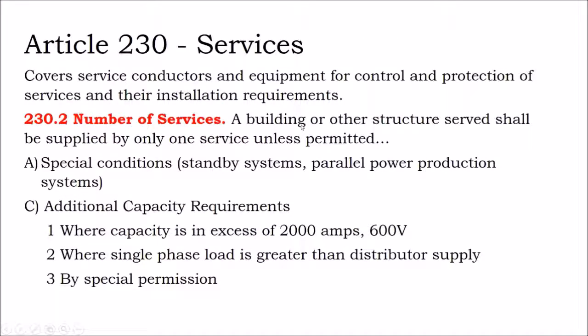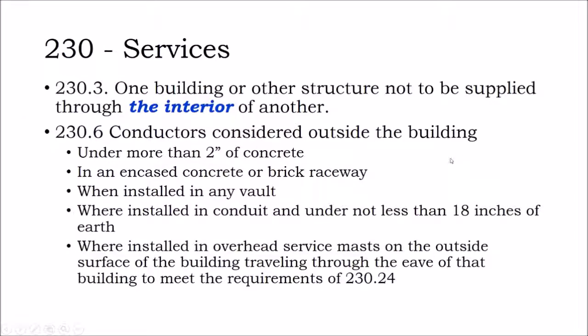So what I'm saying is, if you're thumbing through code and you look at just a general section that says services, and it says you have to put a single line diagram placard here if it's over 600 volts, such as at a higher voltage substation, you might find that when you get into the 1,000-volt section of the inverter equipment down in section 690 or past that, they have similar requirements. Number of services. A building or structure shall be supplied by only one service except for these special conditions. I think I'm kind of repeating slides here.